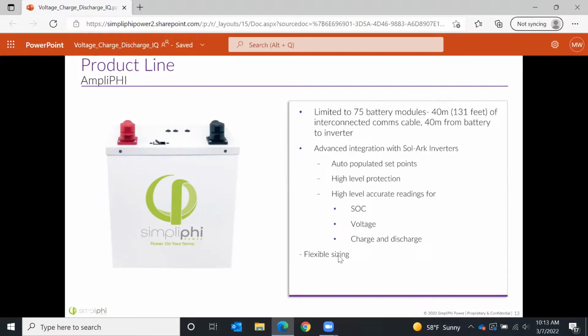Now, on the smaller end of things, another big advantage here is flexible sizing. So a lot of you gripe and moan about our sizing requirements, saying, why do I need to size accurately to this 8 kilowatt inverter? The customer's only using 4 kilowatts. Well, the Phi battery isn't able to limit its own discharge, so you're going to need a properly designed system. Right? So with the SimpliPhi, it's going to communicate to that inverter to limit the inverter's discharge rate. If that inverter, for whatever reason, doesn't respect the demands, it's also going to internally have an added form of protection against discharging and charging too quickly.